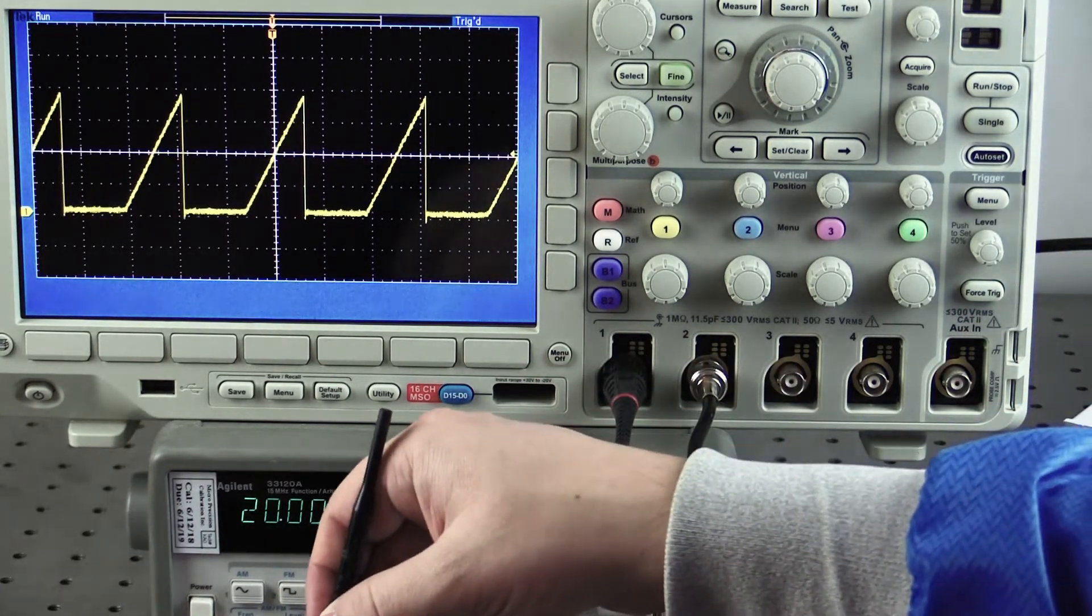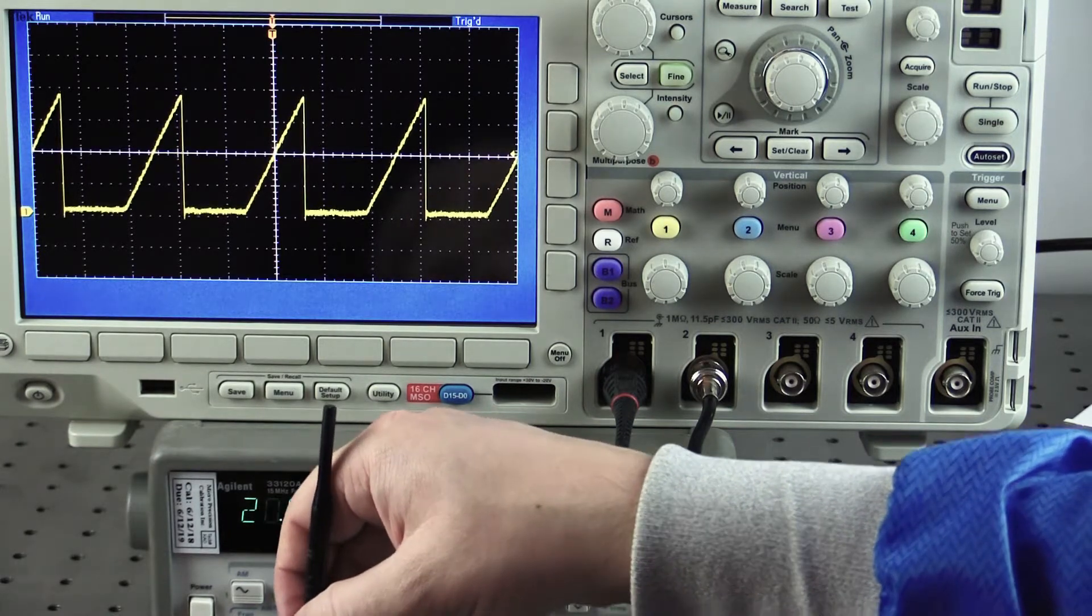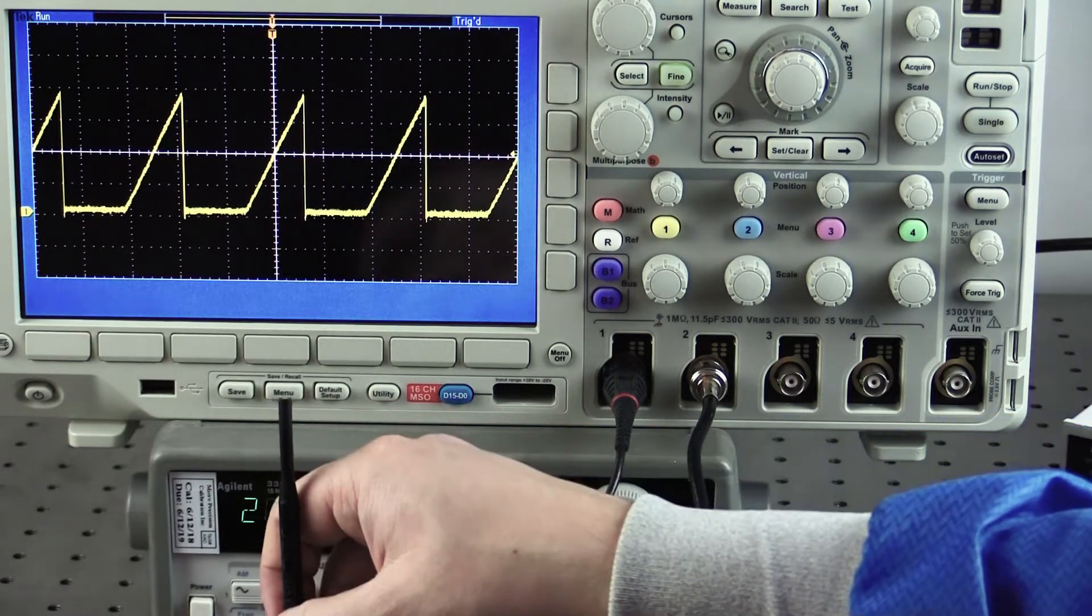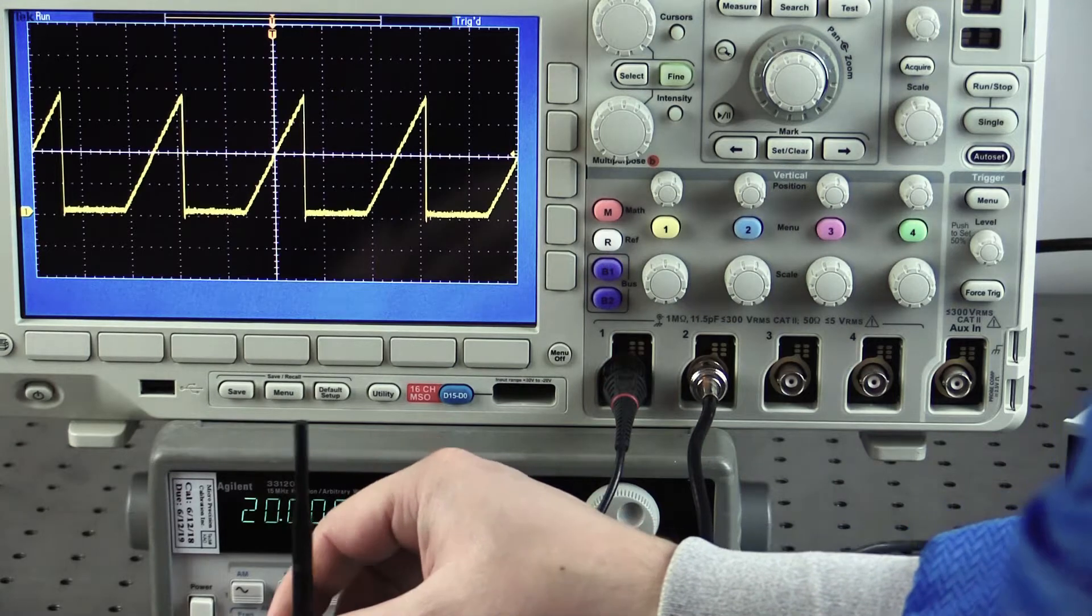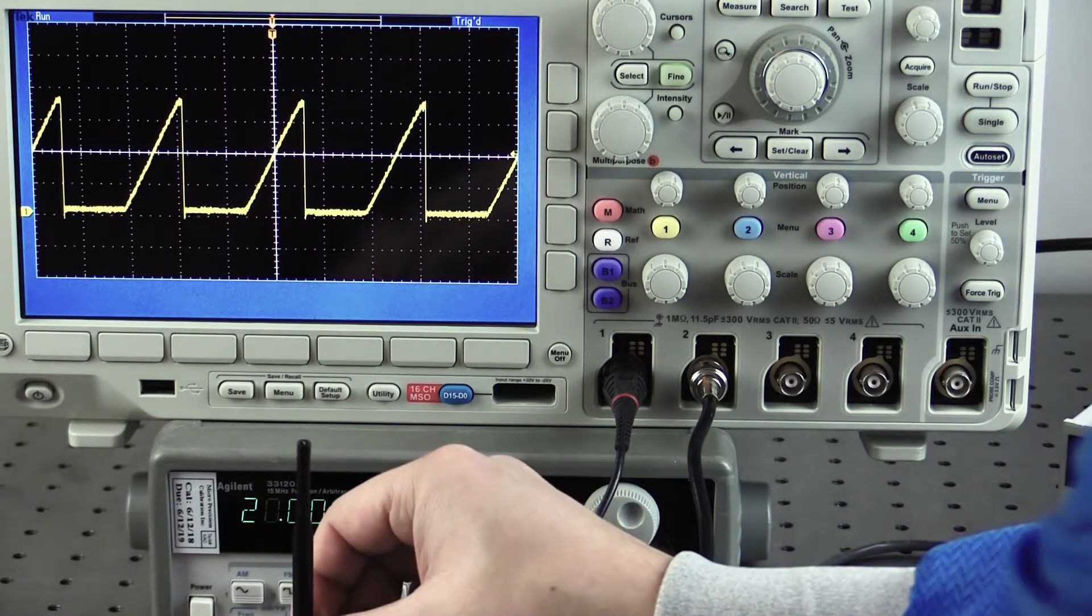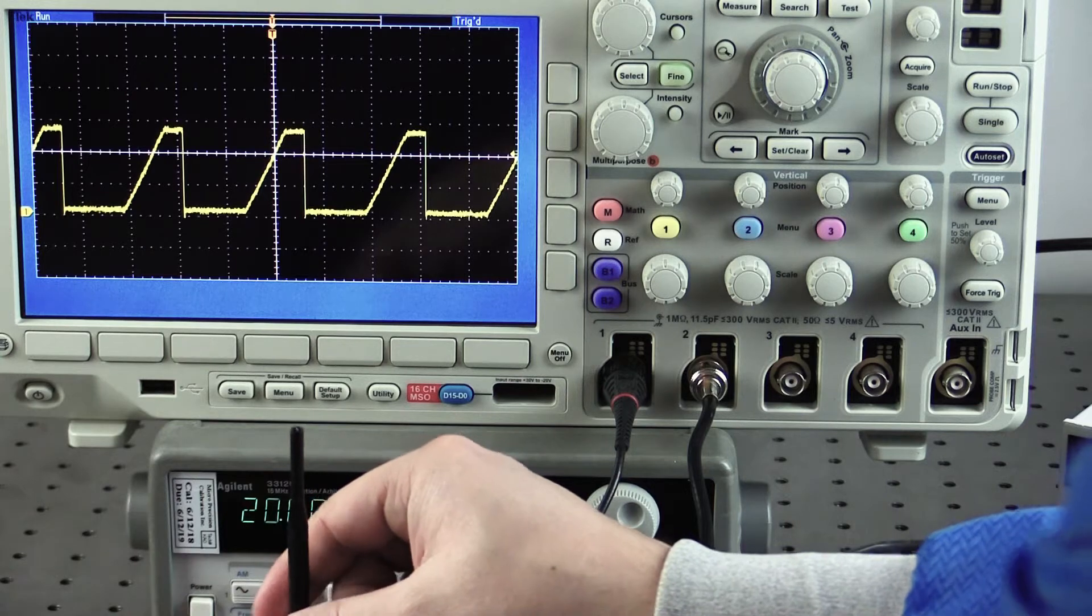To see the impact of the current limit on this external set point, turn the ILIM trim pot counterclockwise until the top of the sawtooth wave becomes flattened. The output current will not increase beyond the limit.